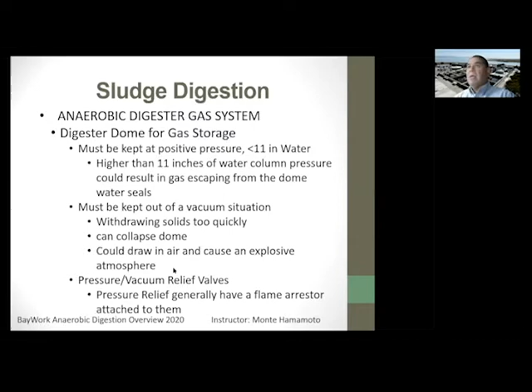So it's very serious. It's something we watch as operators very closely, because we know these things can happen, and we want to make sure we don't have it happen at our facility. So here's those safety devices, and you'll see these sitting on top of the digesters. You'll see that square box in the bottom, what they call pressure vacuum relief valves, is a flame arrestor, and it's a series of aluminum plates where the flame actually has to make its way through these plates, and generally it can't. So it actually blocks any flame that may be from the outside, and it blocks that flame from getting back inside the digester where the gas is.